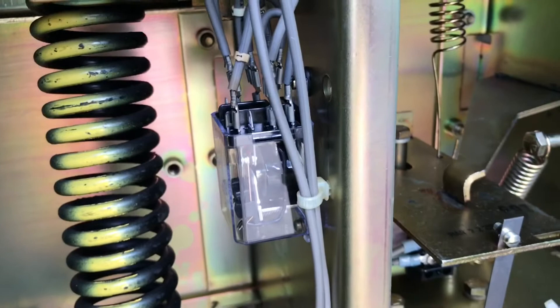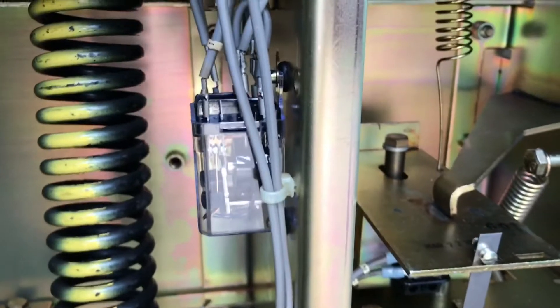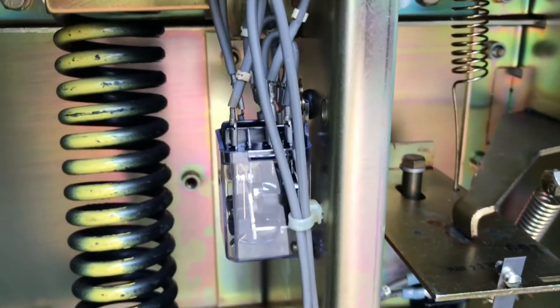All right, so I got my hand on the control switch now. I reinstalled the springs on the under voltage, so it's going to trip free. But I'm just going to show that if it trips free and that control switch remains closed, that anti-pump relay is going to remain closed the entire time as well.